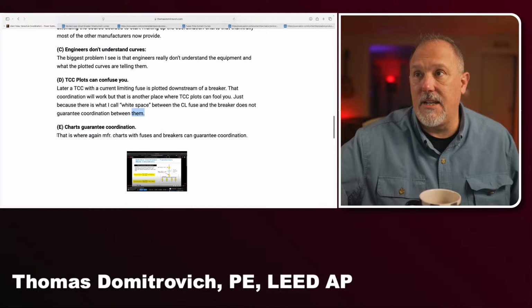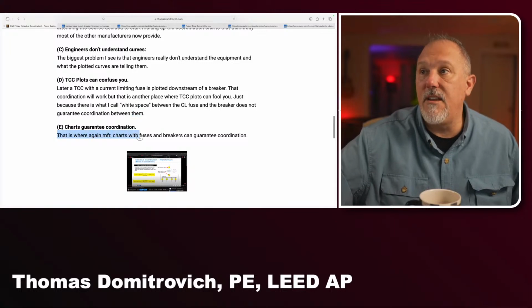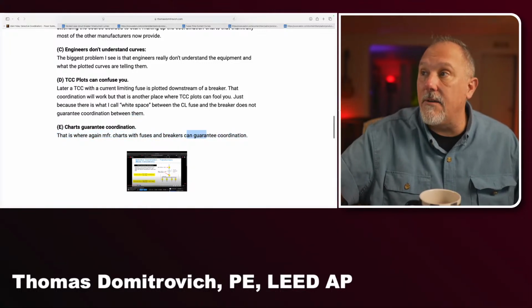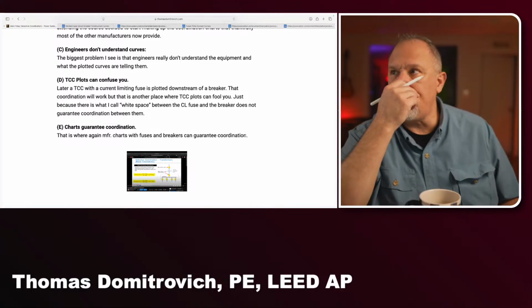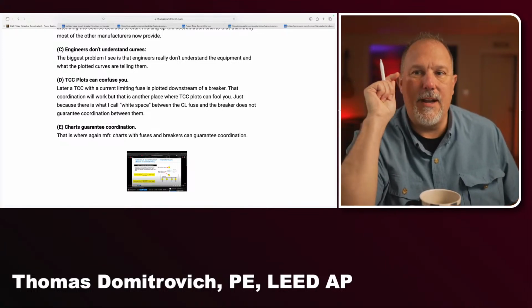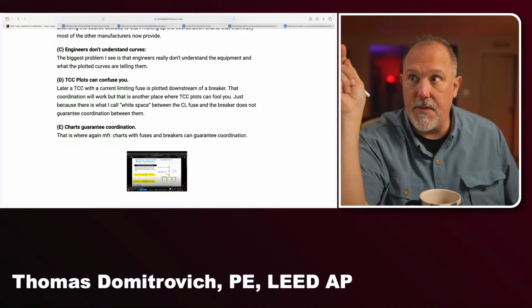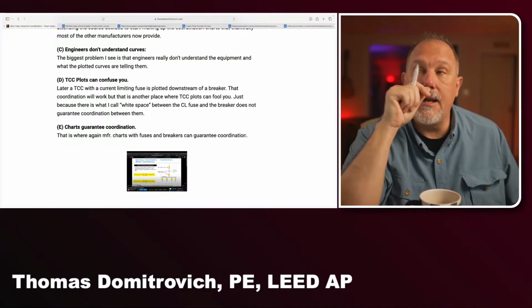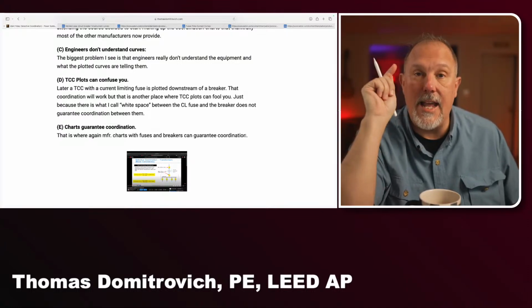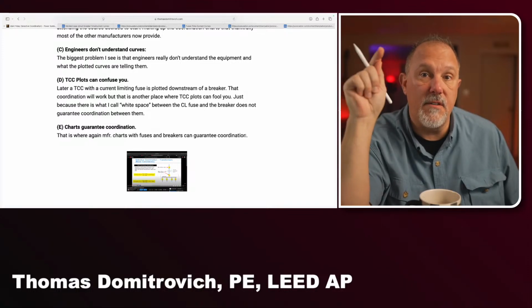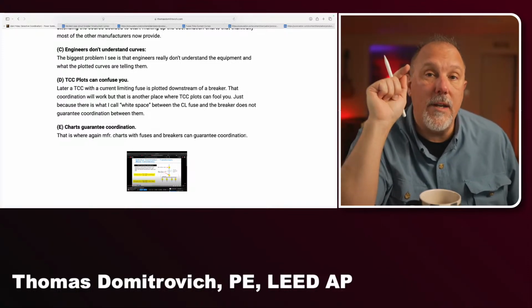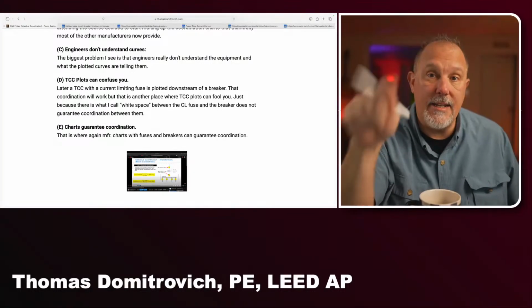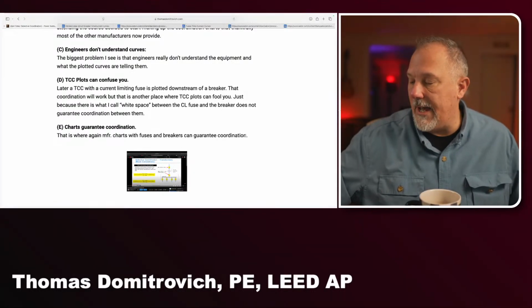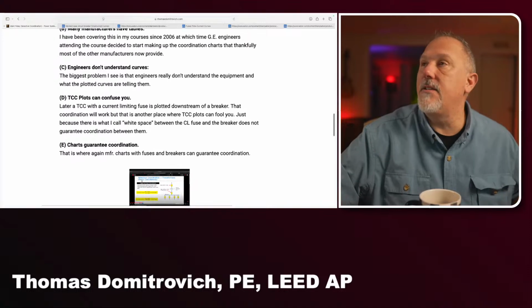Now, here's the other statement he made. That is where, again, manufacturer charts with fuses and breakers can guarantee coordination. Here's the issue I have with it, I don't necessarily disagree with that. Manufacturer's charts can guarantee selectivity at the three-phase bolted fault current value. I'll tell you what charts do not give you. If I look at, let's do this.